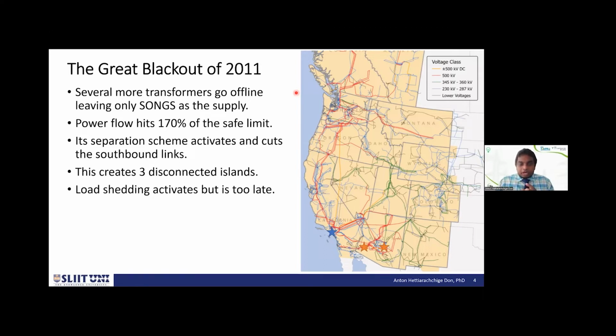So then load shedding starts taking place. That means certain big loads are taken offline so that the generators within those islands are able to supply the load. But all this happens fairly late, it takes time. So the frequency goes down and the generators shut off. Within 10 minutes of this whole thing starting, all three of these islands go into blackout, meaning they lose all power. The generators shut down, they're not connected to the rest of the grid, and it's a total blackout.